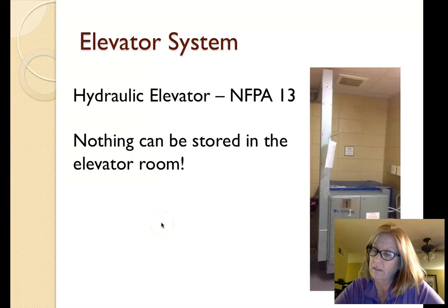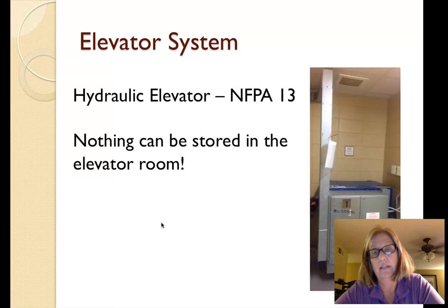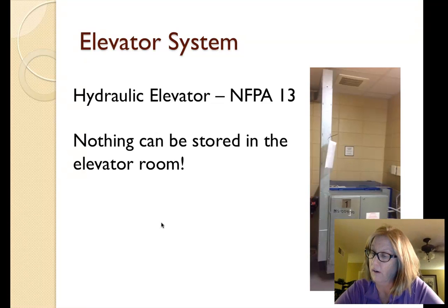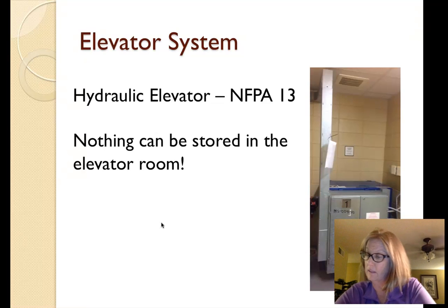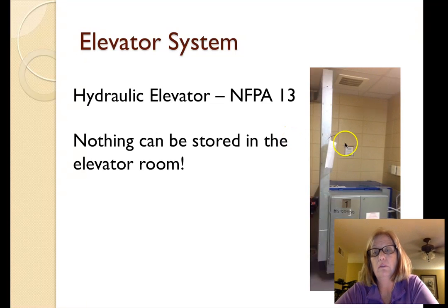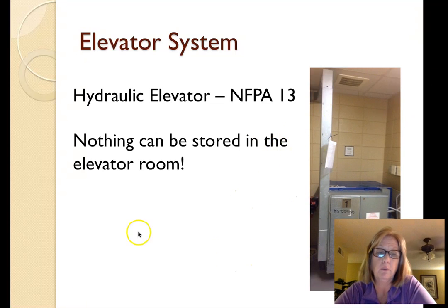So what happens is that everything is done in sequence, and NFPA 72 says that the smoke detector will activate the elevator to come to the first floor. The second thing that occurs is the heat detector activates at 135 degrees Fahrenheit, causing what they call a pre-action, so that all of the high voltage electrical system will be shut off, and then the sprinkler will activate at 155 degrees. All of the heat detectors are rate-of-rise detectors that are based on time. As you can also see, I know my picture's in the way a little bit, but the elevator room was completely clear of everything but the elevator equipment.